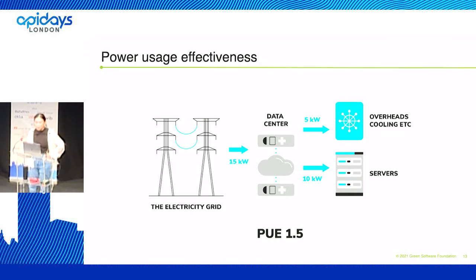It's a way for us to conceptualize how much energy is needed to support our application in a particular data center. For example, if our application consumes 10 kilowatt hours, and the PUE of the data center is 1.5, that means we actually need 15 kilowatt hours from the electricity grid, where 10 kilowatt hours go to the servers, and 5 go to the overhead activities.